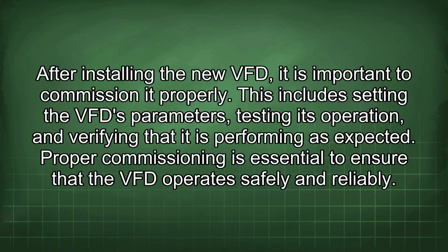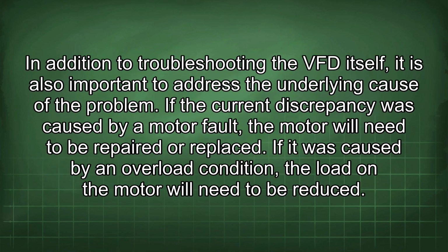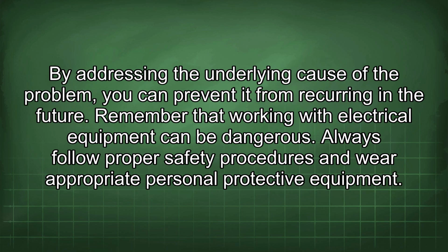After installing the new VFD, it is important to commission it properly. This includes setting the VFD parameters, testing its operation, and verifying that it is performing as expected. Proper commissioning is essential to ensure that the VFD operates safely and reliably. In addition to troubleshooting the VFD itself, it is also important to address the underlying cause of the problem. If the current discrepancy was caused by a motor fault, the motor will need to be repaired or replaced. If it was caused by an overload condition, the load on the motor will need to be reduced. By addressing the underlying cause of the problem, you can prevent it from recurring in the future.